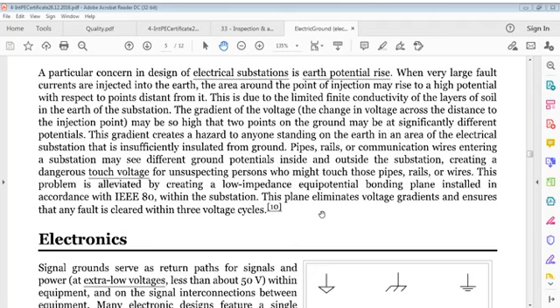entering a substation may see different ground potentials inside and outside the substation, creating a dangerous touch voltage for unsuspecting persons who might touch those pipes, rails or wires. This problem is alleviated by creating a low impedance equipotential bonding plane installed in accordance with IEEE 80 within the substation. This plane eliminates voltage gradient and ensures that the fault is cleared within 3 voltage cycles.